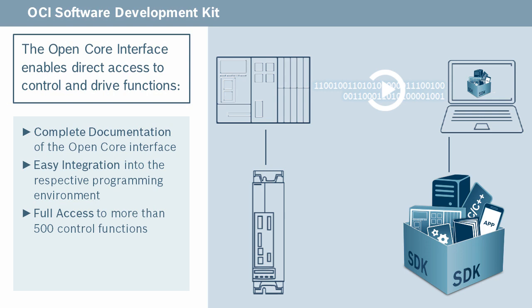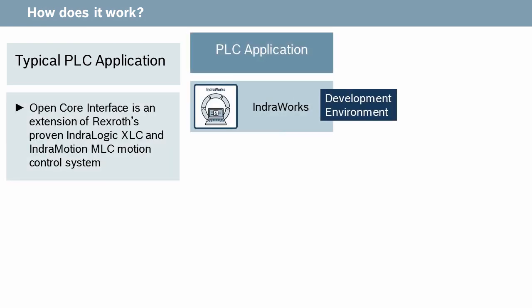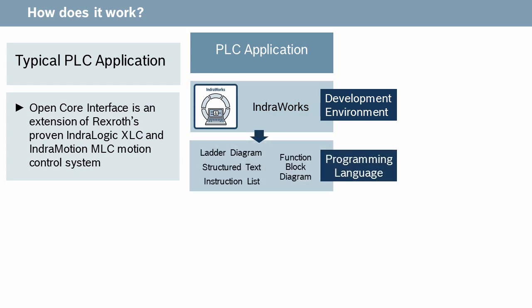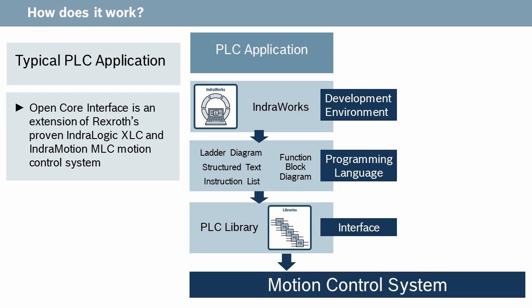It's a library with over 500 different functions to perform motion commands and gather status information about our motion products. The way it works is very similar to the way a PLC application works in the controller. There's a CODESYS 3S system on top of the motion control system. The application engineer writes a PLC program in IndraLogic using Ladder Logic, Structured Text, or another language to access commands in PLC libraries, and then those libraries talk to the firmware — more under the hood — to actually create motion in the system.